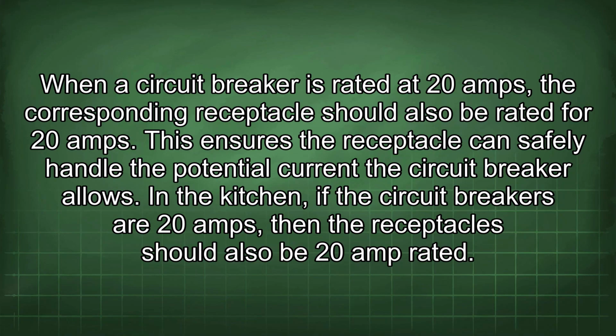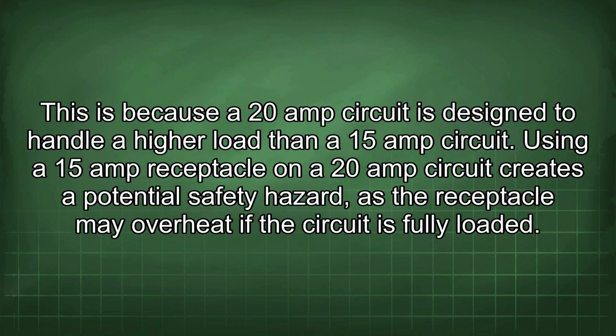When a circuit breaker is rated at 20 amps, the corresponding receptacle should also be rated for 20 amps. This ensures the receptacle can safely handle the potential current the circuit breaker allows. In the kitchen, if the circuit breakers are 20 amps, then the receptacle should also be 20 amp rated. This is because a 20 amp circuit is designed to handle a higher load than a 15 amp circuit. Using a 15 amp receptacle on a 20 amp circuit creates a potential safety hazard, as the receptacle may overheat if the circuit is fully loaded.